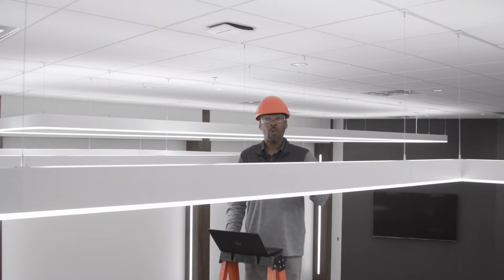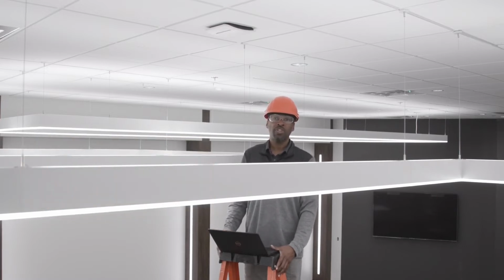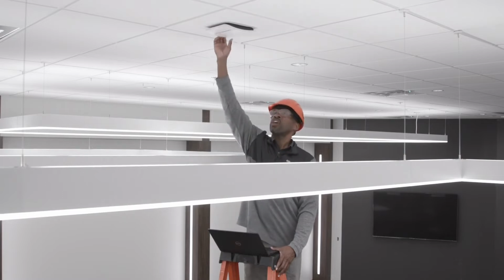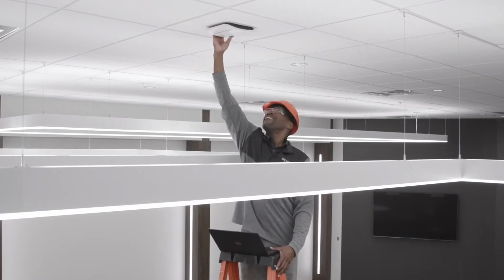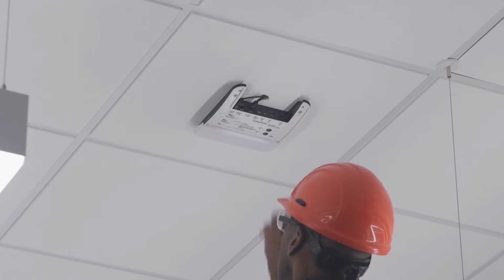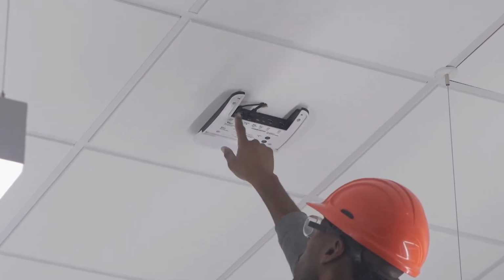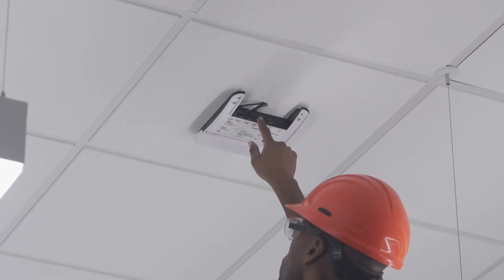So that's the reason why I'm standing on the ladder now, so you can see how we may need to change the WAC configuration. To open up the WAC and change the configuration, you need to do the following. One, take the face cover off the WAC. When the front cover is removed, you'll see that there are ports on the WAC.